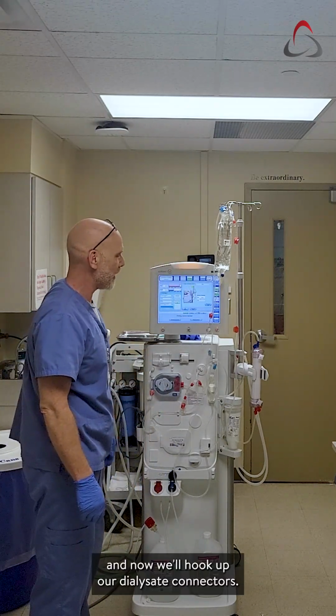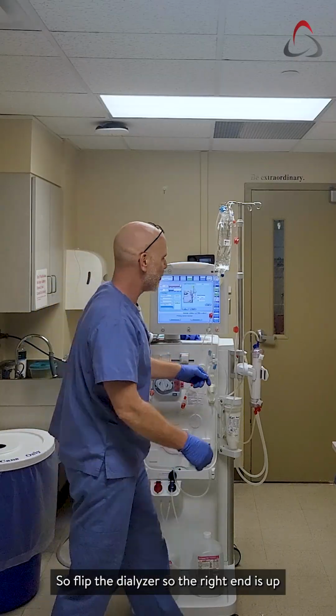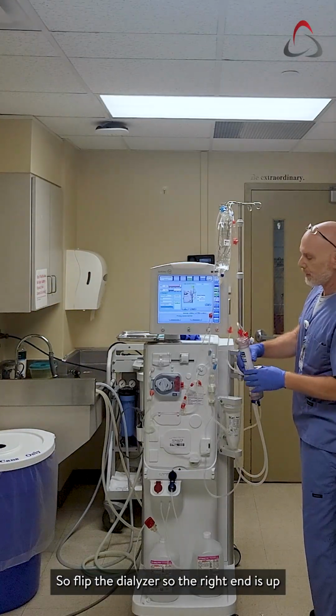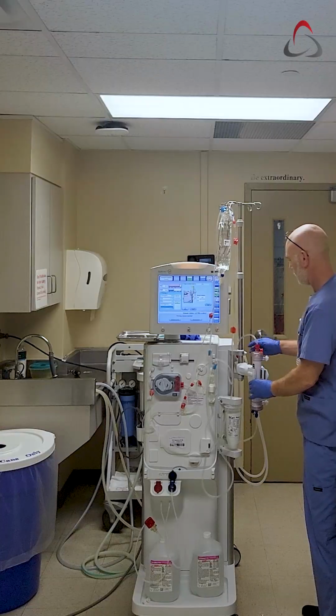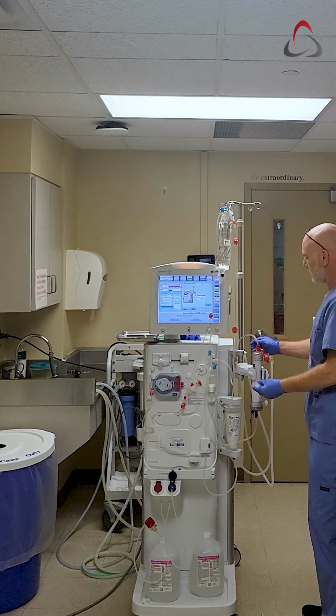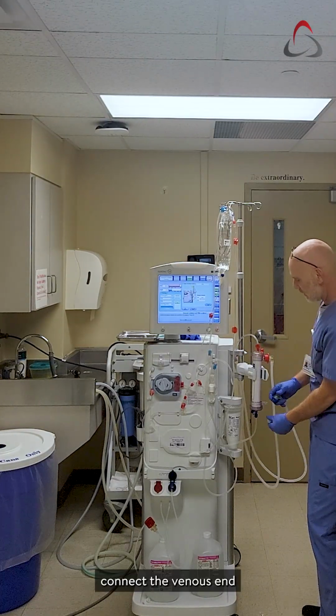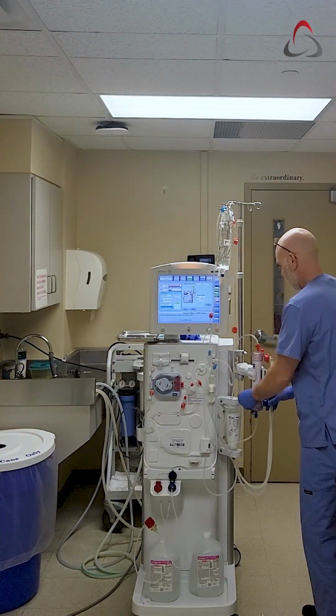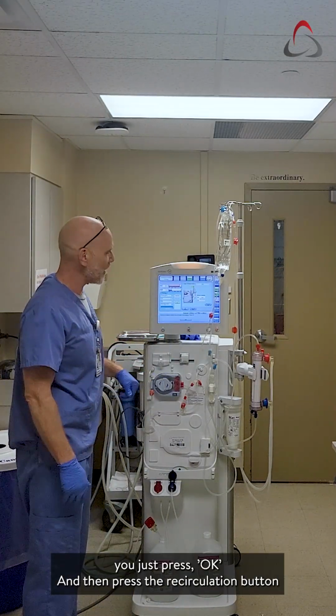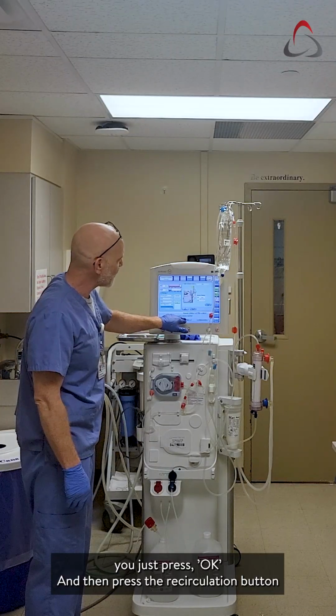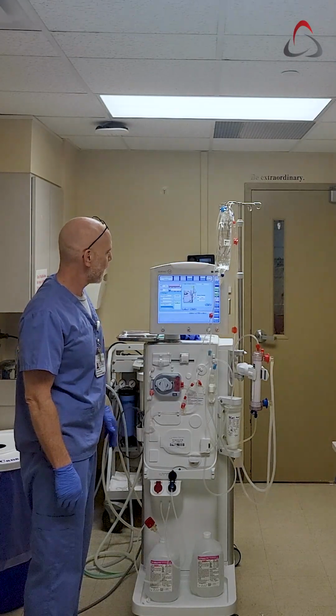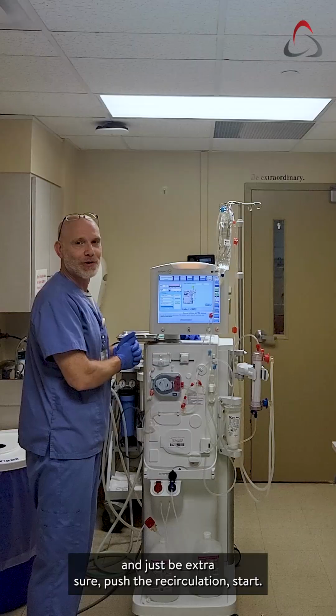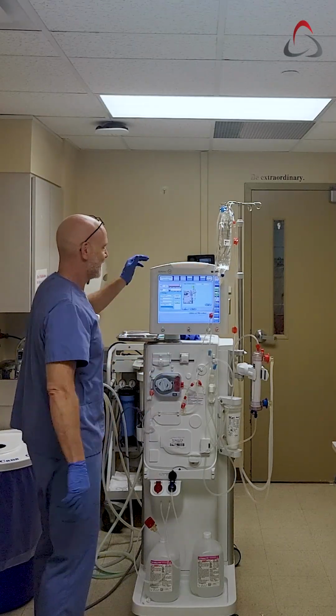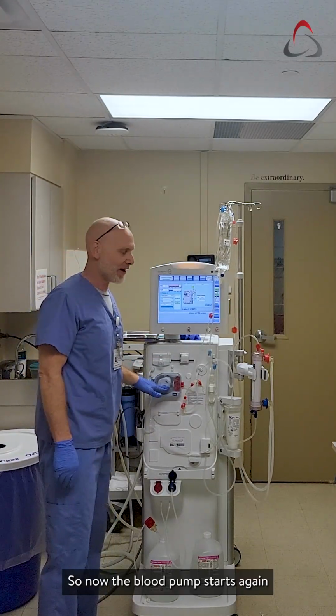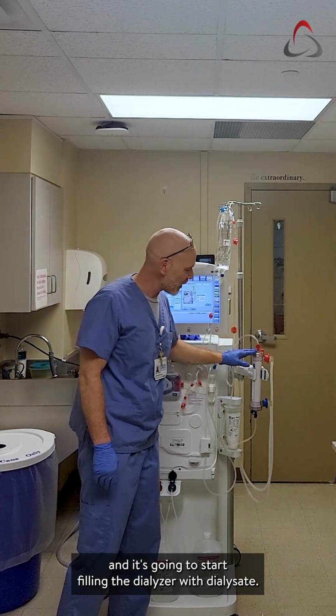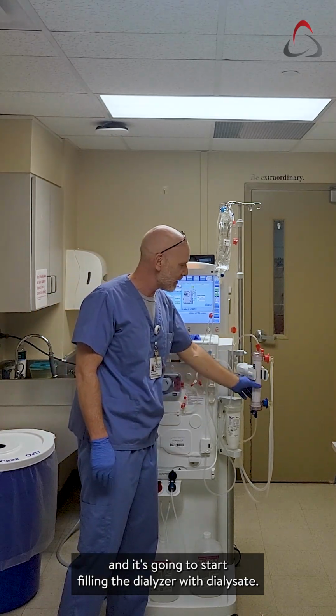And now we'll hook up our dialysate connectors. So flip the dialyzer so the red end is up. Connect the arterial side. Connect the venous end. And once you've done all of that, you just press OK, and then press the recirculation button. And just to be extra sure, push the recirculation start. So now the blood pump starts again, and it's going to start filling the dialyzer with dialysate.